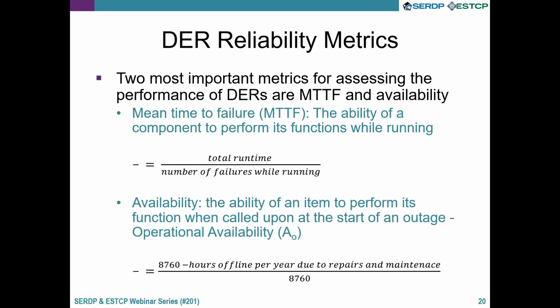The first is called the mean time to failure, and that's exactly what it sounds like. It just says that when a component or generator or PV is running, how long does it run on average until it fails? This can be quantified from empirical data as the total runtime divided by the number of failures while running. So it gives you a sense: if it's very long, it's very unlikely they will fail. If it's very short, the system will fail quite quickly during an outage.